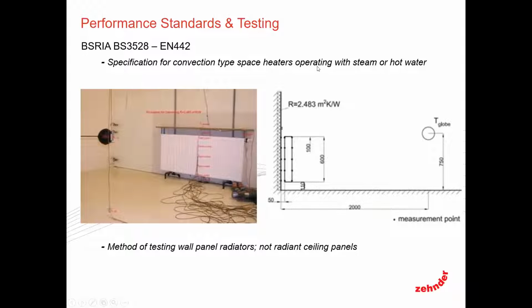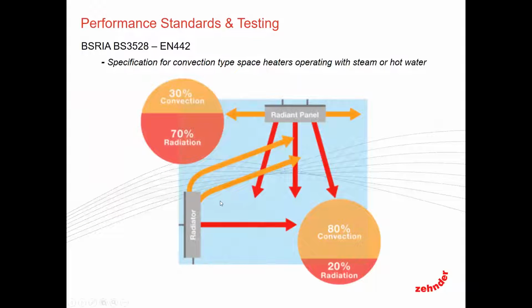space heaters. So what happened a number of years ago was, as radiant manufacturers globally started releasing product into the market, they saw that there's no standard testing. They said, oh, wow, hey, we have these EN442 labs already approved. Let's just stick it on the wall and measure the performance of the radiant panel. Well, what are you measuring? You're measuring a panel radiator at that point. And what happens is, when you take that ceiling panel and put it on the wall, you get output somewhere near 80% convective, 20% radiation. And then when you change the configuration and put it in the ceiling, you get 70% radiation, 30% convective. So by changing the orientation in the space, you're changing how that panel performs.